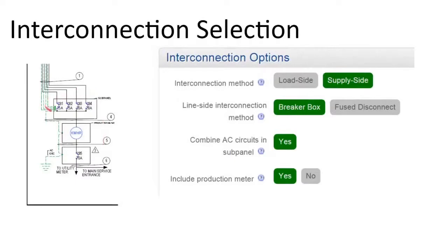It's modeling our sub panel with the microinverters all landing on different branch circuits, and then tying into a solar production meter, going through a main disconnect breaker, and then heading out to either the utility main service panel or the utility meter, because it's been denoted as a supply side connection. So these one line diagrams do get automatically generated at some point in the chain.